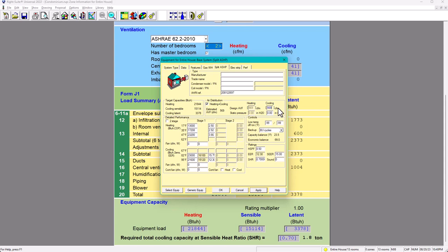But you might be wondering, but wait a minute, Roberto. What you said you're gonna put a 2-ton unit, 2-ton, and you have 400 CFM per ton, so you would need an 800 CFM in here, and that is correct. So this is the target CFM, and then later once we select the system, we're gonna convert this target CFM into a design CFM. Okay, with the design CFM, we're going to do the duct sizing.